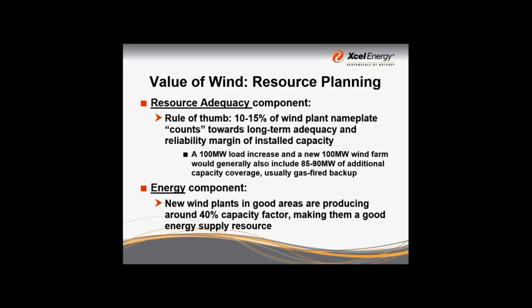If we had a 100 megawatt wind farm, from the resource adequacy standpoint we might only count 10 to 15 megawatts of that capability towards our reliability margin, and have to procure 85 to 90 megawatts of other dispatchable resource in case the wind wasn't blowing. That's one value, and because of that discount, it's typically not the basis by which wind and solar are selected in our resource plan.